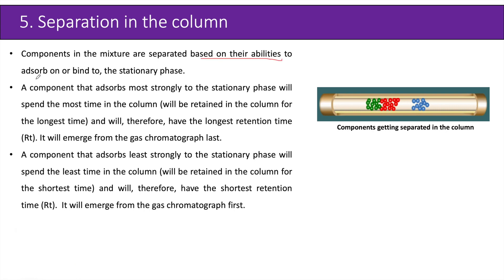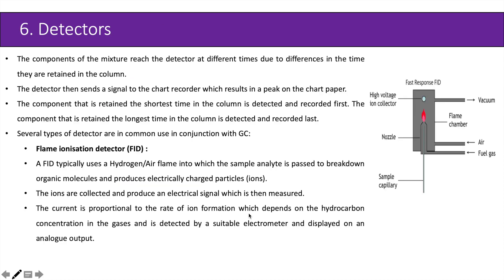The next step is separation in the column. Components in the mixture are separated based on their ability to adsorb or bind to the stationary phase. A component that adsorbs more strongly to the stationary phase will spend the most time in the column, having the longest retention time, and will emerge from the gas chromatograph last. A component that adsorbs least strongly will have the shortest retention time and will emerge from the gas chromatograph first.